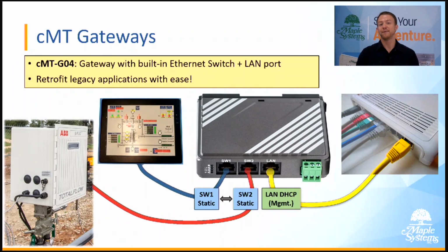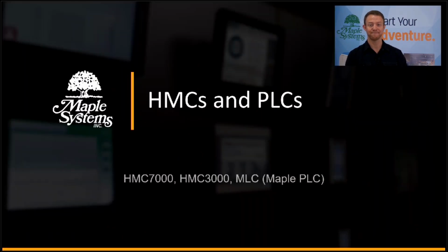I have a diagram here now showing you how you could actually set up the networking with the cMT G04. So you can have your PLC and HMI just plug in directly to those switch ports, and they'll be able to communicate with each other as if nothing has changed. At the same time, you have the LAN port for management, and from there you can get data out and see what's being sent back and forth between those two devices, log it, and so on. So you can retrofit a legacy application with ease this way using the smart gateways.